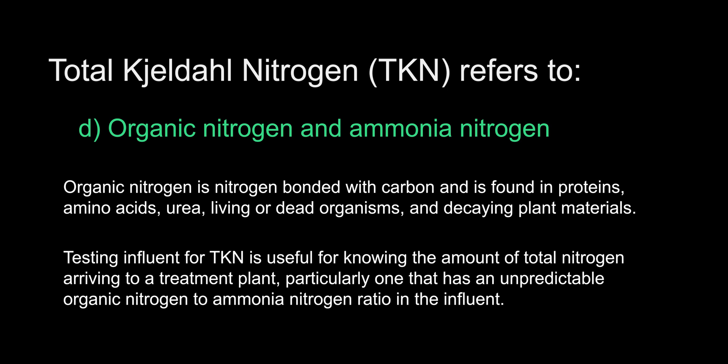To help understand why TKN is useful, we need to understand what can happen when we don't measure it. If you are at a treatment plant that nitrifies and only measure the ammonia content of your influent, you may notice when you test your secondary clarifier effluent for nitrate that you have a much higher value than what the ammonia coming into the system was. That is because the amount of organic nitrogen coming into the plant was not accounted for. TKN allows us to understand the total amount of nitrogen coming into the facility so we can accurately manage the nitrification process.